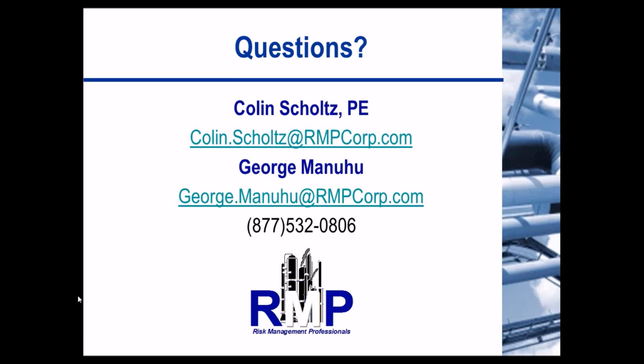That is a good comment, and George did a good job summarizing it. And I think a lot of times when general maintenance is done on equipment, like the painter comes, painting over a nameplate happens more frequently than you would think. And that's an issue because if that nameplate can't be found, then you don't have any information on your system and you could potentially be exceeding design limits.